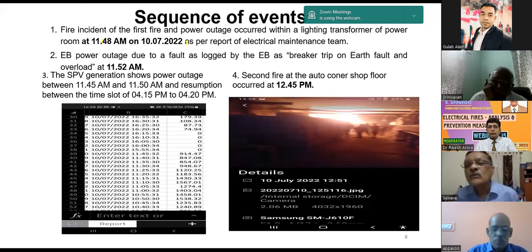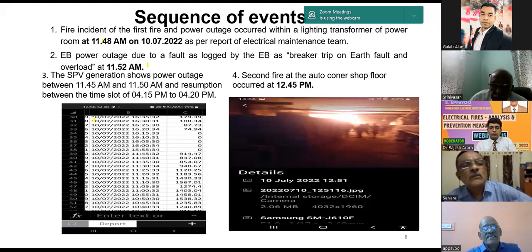So we should ascertain the power failure timing also. It was ascertained from the electricity board that it was 11:50. There could be some manual error in assigning timing between the board people, the logbook, and the company people. So I had one more reliable way of ascertaining the time. I assessed the SPV generation. The textile mill had an SPV generation. If you know that SPV will generate, it will not generate during a power failure. So I ascertained the power every 5 minutes. It's a slot of 5 minutes.